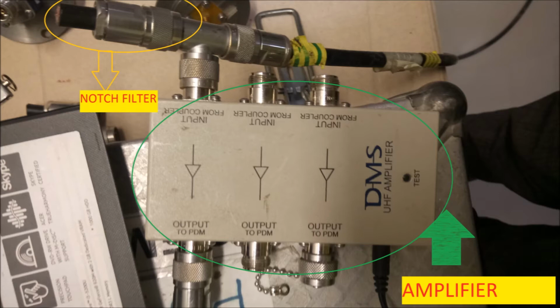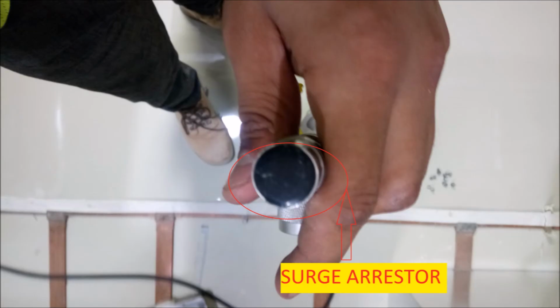Now we will discuss the step-by-step procedure, which is really simple, in order to measure the PD signal. The first step is to open the PD couplers which are placed on the GIS to connect the kit leads. The kit basically consists of an amplifier which amplifies the PD signal before it enters our laptop, because these signals are really weak in nature.